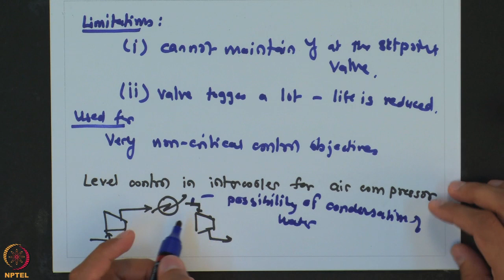So, at that point there is a requirement that you collect this liquid and then remove this liquid after the heat exchanger. Now, as it turns out, this level builds very slowly, and typically there is no objective in terms of controlling this level apart from the fact that you do not want this particular vessel to get completely filled. So, the level control on this after cooler is typically an on off type of controller, which controls a solenoid valve at the outlet. When this level goes beyond a certain value, this valve will open and empty out this entire contents. Again it will get closed when the level goes below the desired value, and then the system will again operate till the level gets filled up.